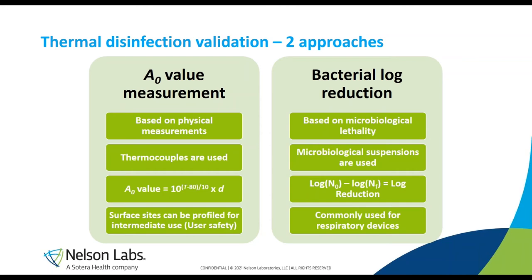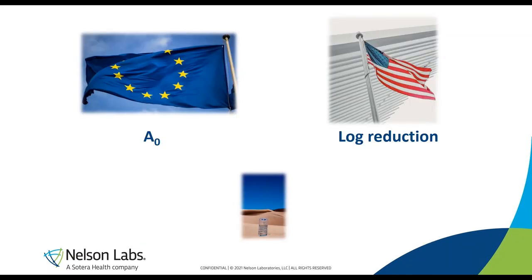The other approach is the bacterial log reduction — more based on microbiological lethality. You take microorganisms in ampules or by direct inoculation on the device, place the inoculated device in your washer disinfector, and see how many bacteria were killed. This is mostly used for respiratory devices. The A₀ method is preferred for the European market, while the log reduction approach is what US authorities want.